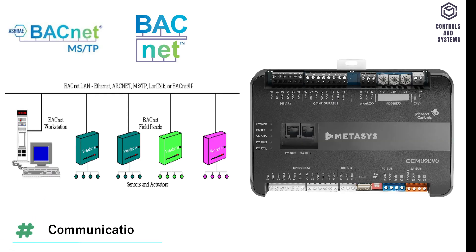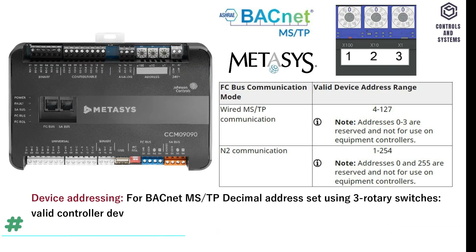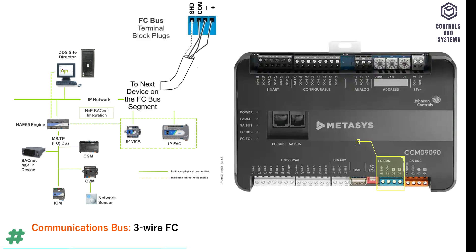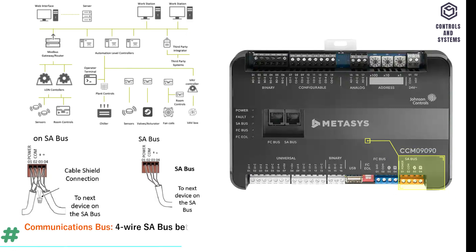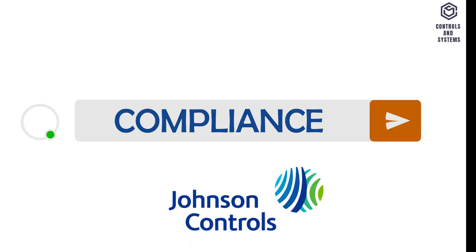Communications. Communications protocol is BACnet MS/TP and MetaSys N2. Device addressing for BACnet MS/TP and N2 is decimal address set using 3 rotary switches. Communications bus: 3-wire FC bus between the supervisory controller and equipment controllers. 4-wire SA bus between equipment controller, network sensors and other sensor actuator devices, includes a lead to source 15V DC supply power to bus devices.